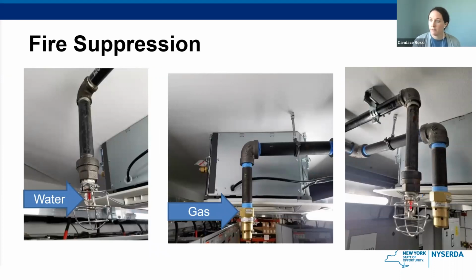So here are images of a fire suppression system. And once again, this is actually from that project that I've stated a few times that's located down in Brooklyn or Queens. This system utilizes both a water and a clean agent gas system. The sprinkler heads on the water have that little glass bulb, and once it's melted out, the water can burst out and come into the system, so it's a bit more automatic that way. And then there's also the clean agent link, which can be put into use by the battery management system as needed.